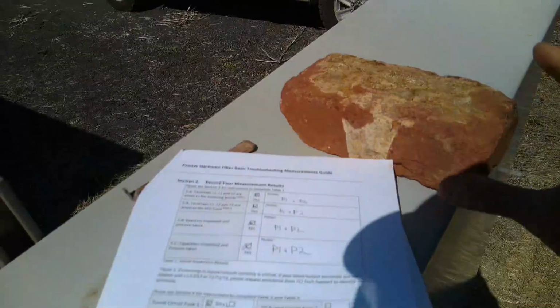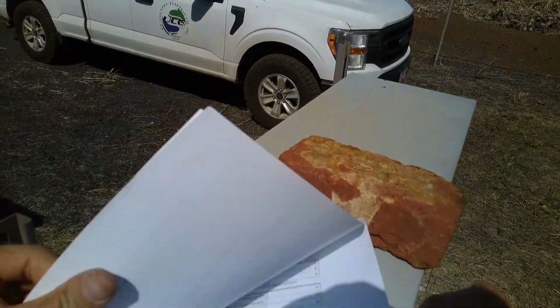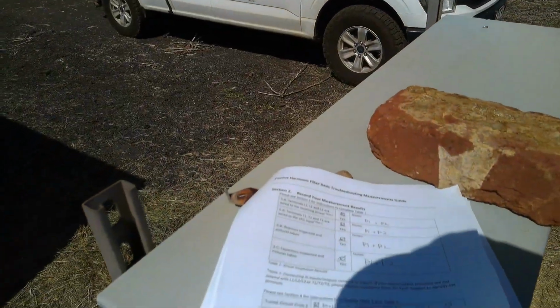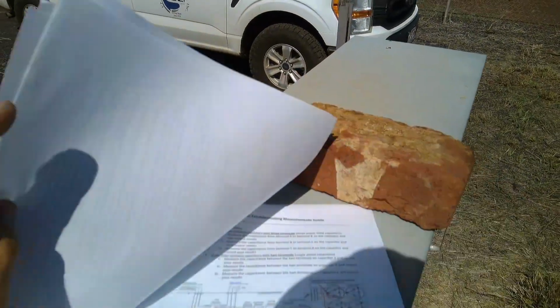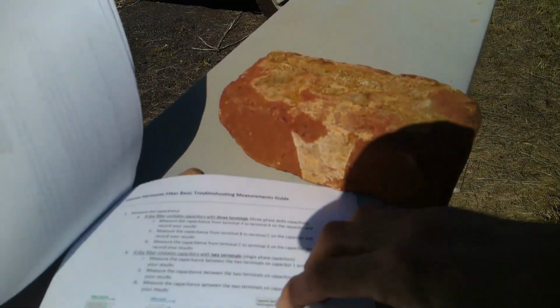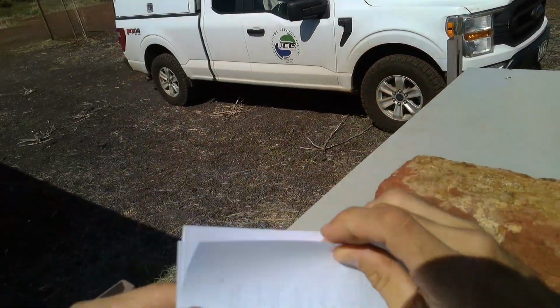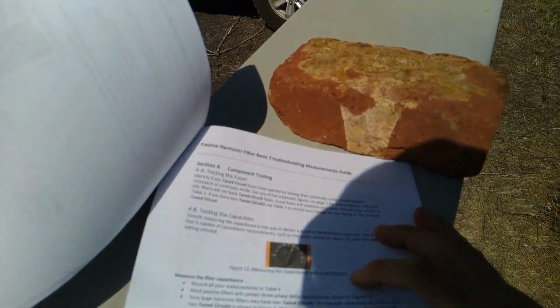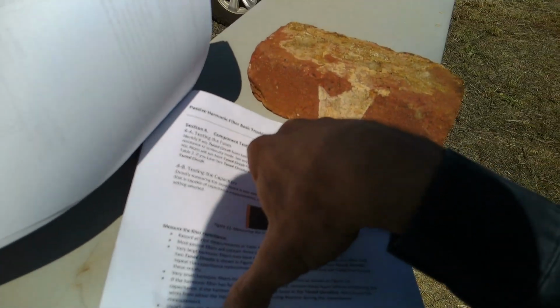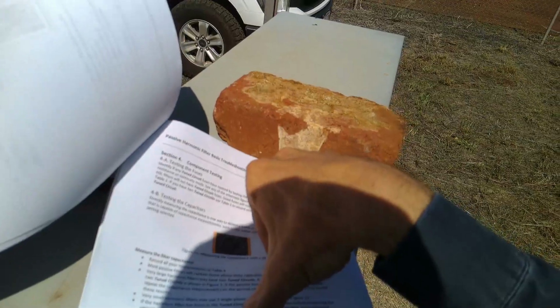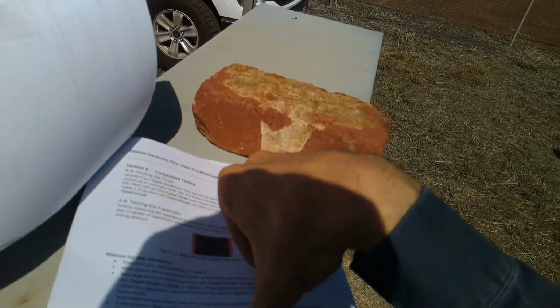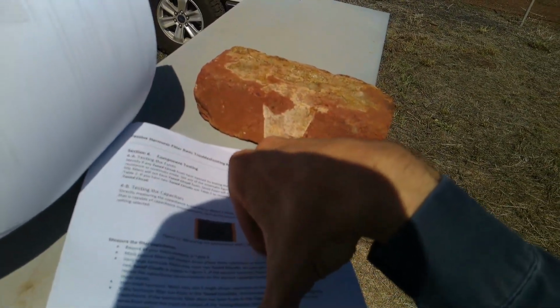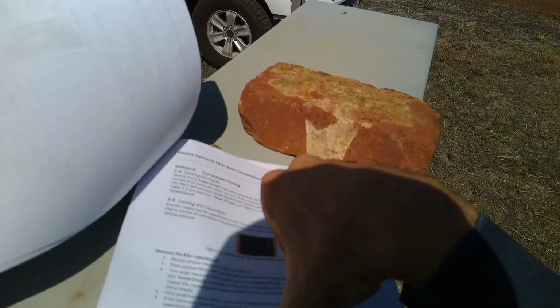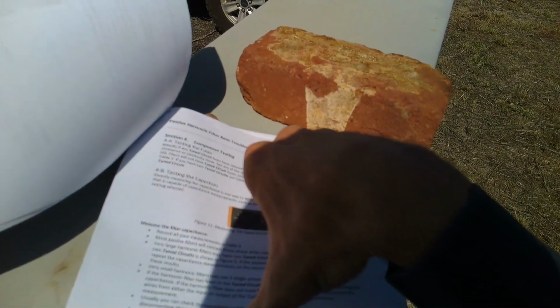So just to double check, these are 3-phase capacitors. Because they're all wired in parallel, what do they say here? They say, select any one capacitor from the bank and make your measurement on it. You only need to make one measurement because all of them are wired in parallel and the capacitances will add together. Perfect.